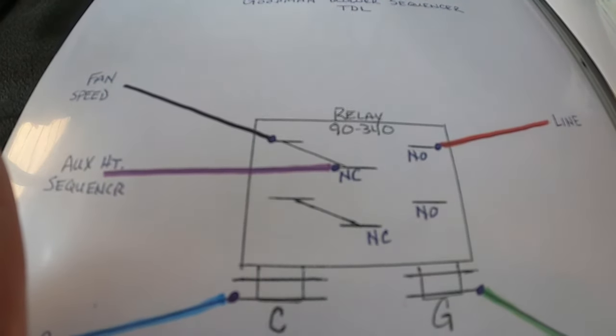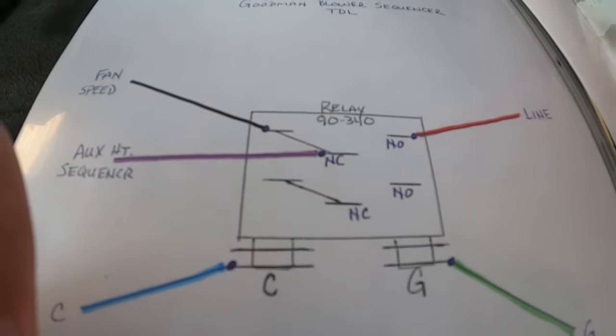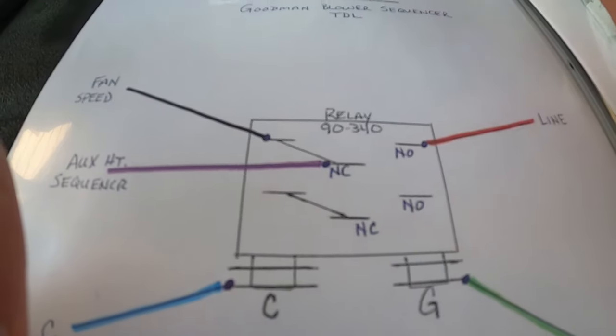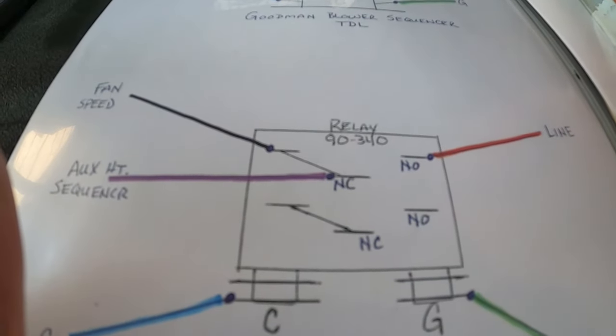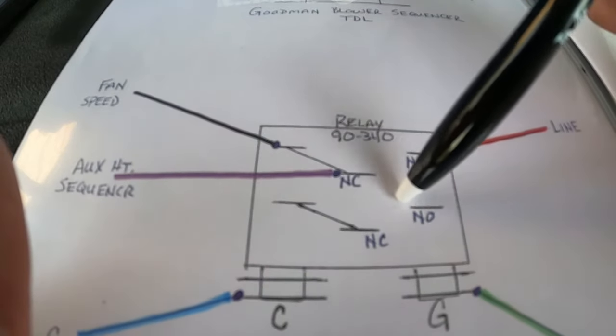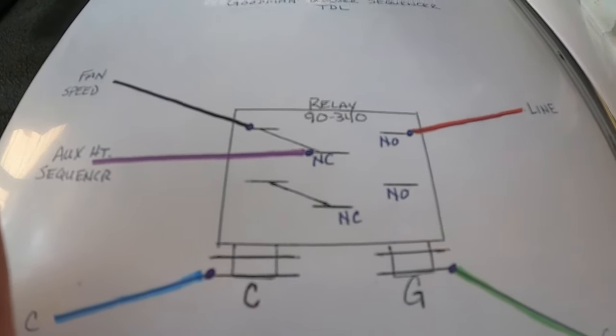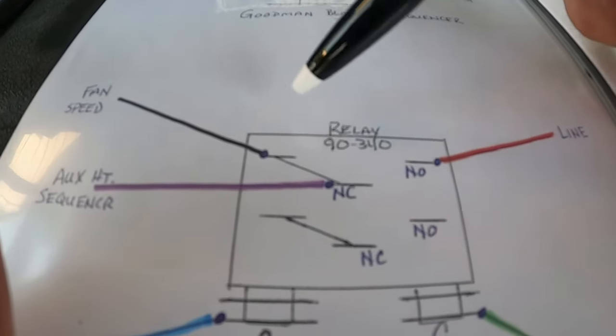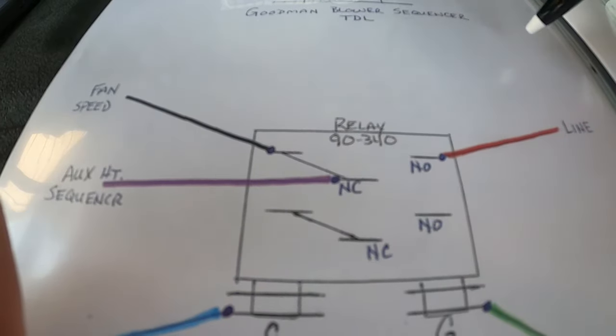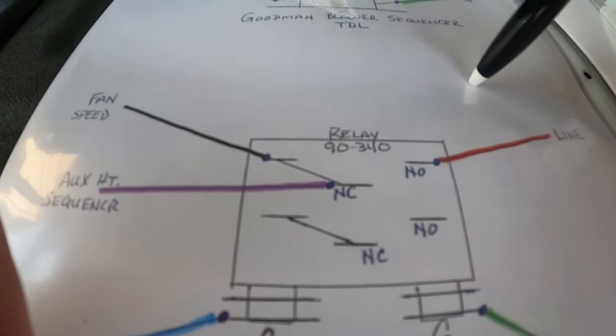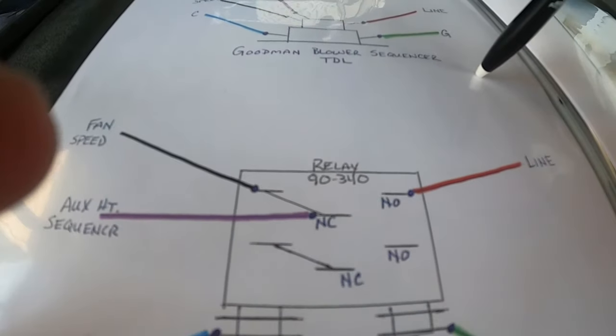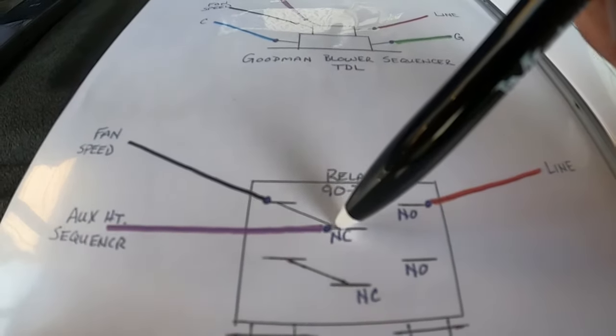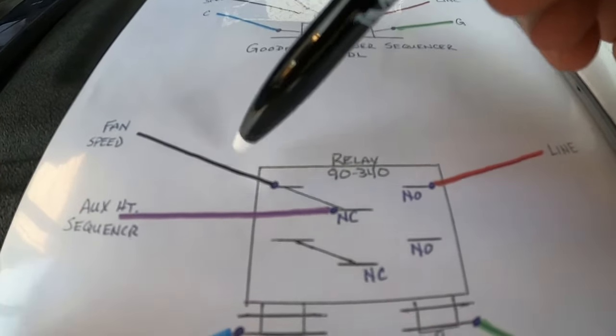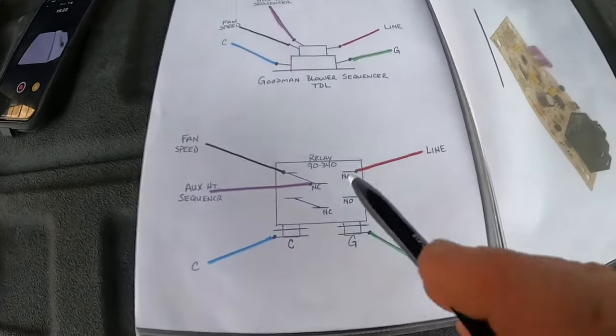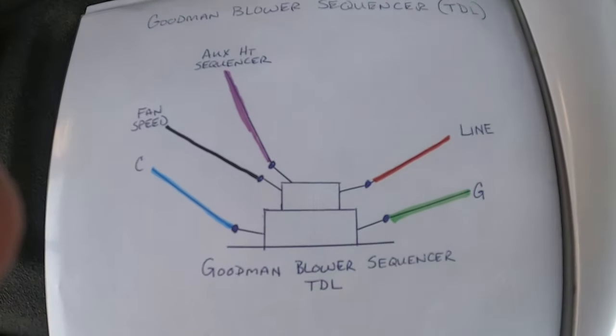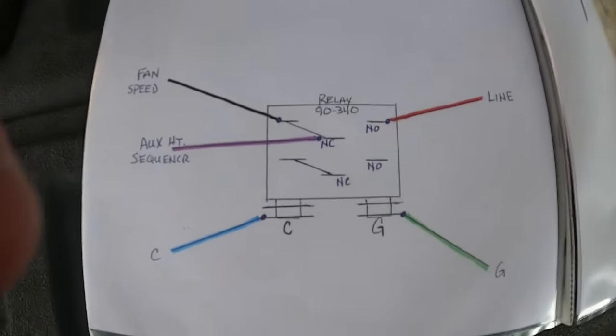If your heat sequencers and your heat strips are running, you don't want those things running without airflow, obviously, that goes without saying. But Carrier does it a certain way, Trane does it a certain way, Goodman does it a certain way. Trane uses the second switch to just simply prove common over to your contactor in your air handler for your heat strips. Most everybody else in most situations is going to have a backfeed off of a heat sequencer, that when that heat sequencer closes, it's going to energize a bank of heat strips, but it's also going to send that power back over here to energize that blower to make sure there's airflow. So that's how you're going to wire that if you're replacing it to that.